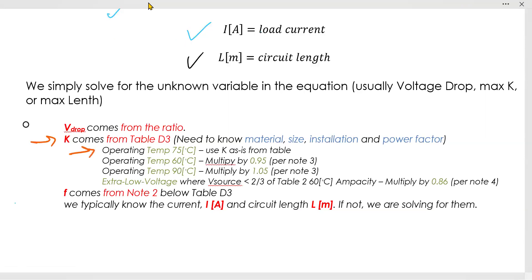Use it by itself if the temperature is 75 degrees. Multiply it by 0.95 if the temperature is 60 degrees. Multiply it by 1.05 if it's 90 degrees. If this is an extra low voltage case where the source voltage is less than two-thirds of the ampacity, then multiply it by 0.86. That's what note 3 and note 4 say.